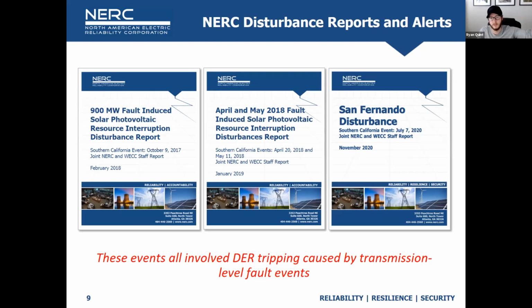So we have a normally cleared fault on the bulk power system. Tree hits a line, whatever it might be, conductor falls and hits other conductors, and we have a fault event as expected, and the transmission level relays operate as designed, and the fault is cleared very quickly, 2 to 3 cycles. And with that, we see 1,000 megawatts of bulk system connected solar drop off, disappear, or cease their injection of power into the grid, which is not to be expected. And more recently, we've been seeing fairly consistent distributed energy resources disappearing. And what that is, we see a net load spike, right? So net load actually goes up because the power that's being provided by the DERs on the distribution system is no longer there. And so there's more load there at the interface. And so we actually see a jump up. And that jump up lasts for 5 to 7 minutes and comes right back down.